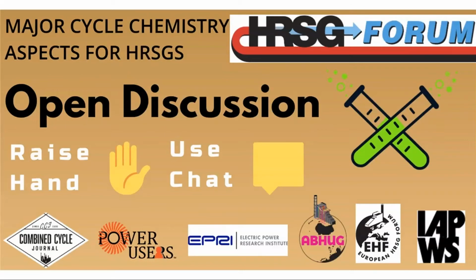Yes. And Ken and Kirk, we try all the time to get the right sample points for iron. We try to get the right sample points to have the instrumentation. We've published extensively the minimum level, but we still find, particularly for you, Andy, which must be horrible, that some of these units don't have steam monitoring. Not only don't have steam monitoring, don't have steam sampling points. And so, I think that's being published. Many organizations have published that instrumentation list that Kirk showed, and similarly for the corrosion products, Ken, right?